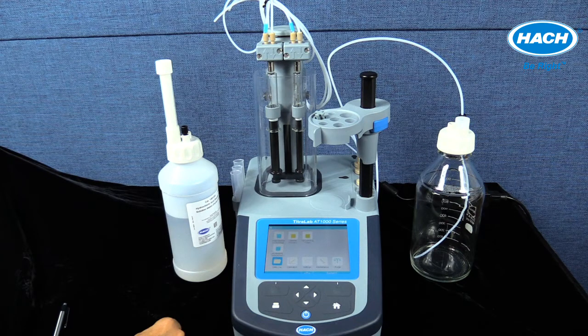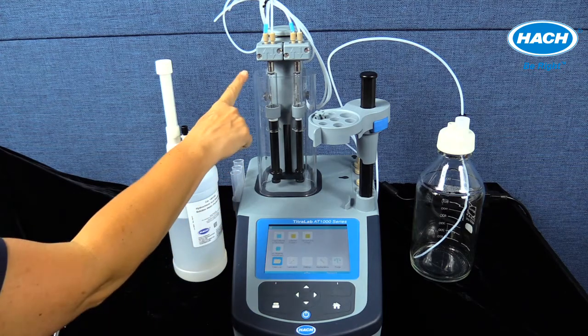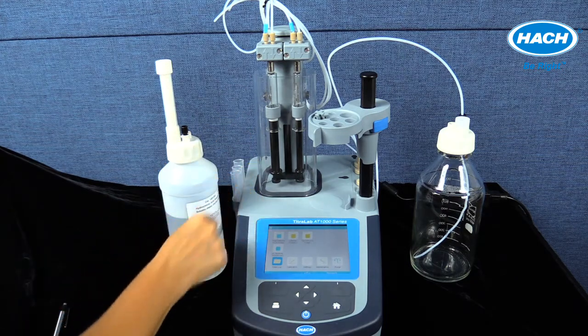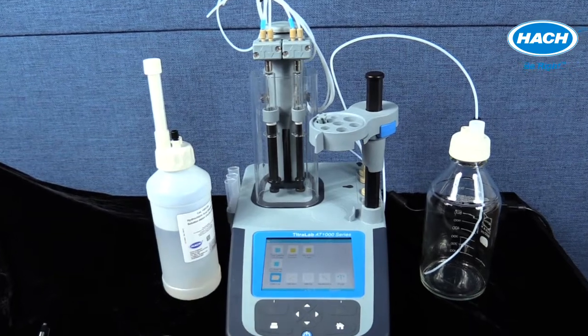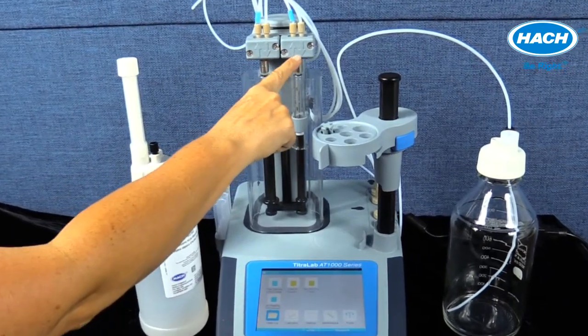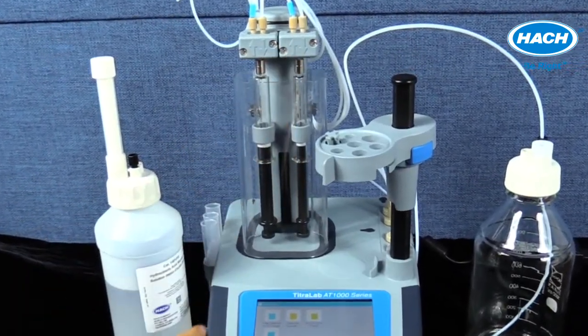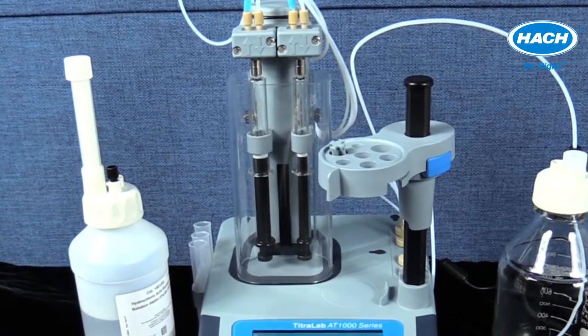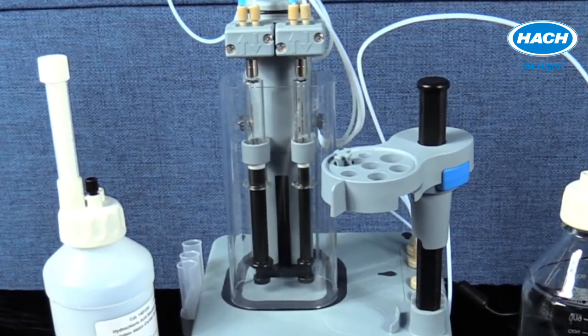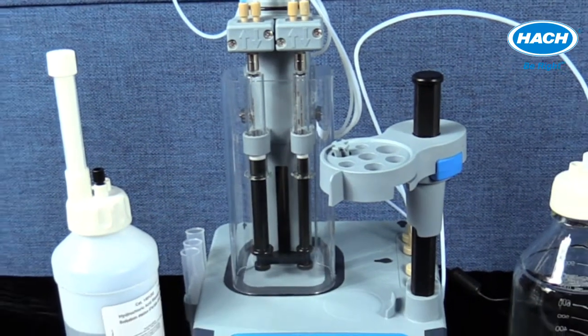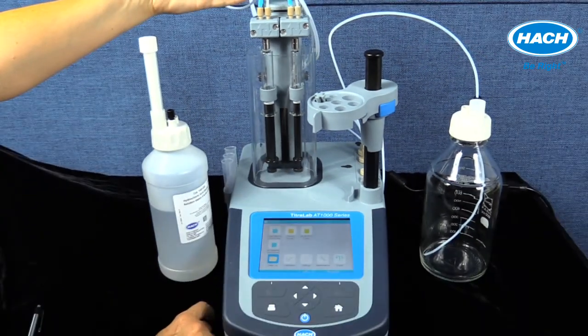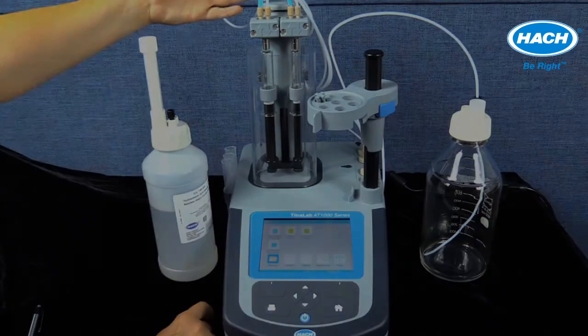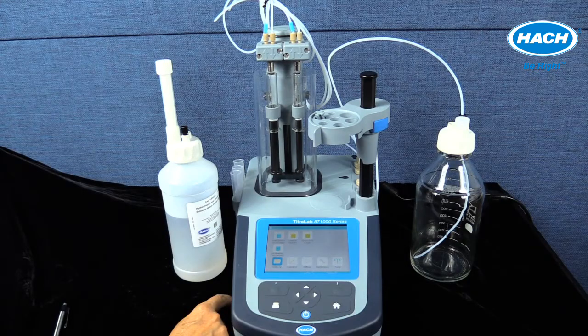For a titration to be accurate, the volume of a titrant being added or dispensed to the sample has to be precisely measured. The AT1000 utilizes a high-quality Hamilton syringe, also known as a burette, and a syringe motor with micro-stepping technology. AT1000 models are available with single or dual syringes. Each syringe has a built-in valve that can divert or stop flow from the syringe. This allows the titrator to utilize different titrants and have access to multiple applications and analyze multiple parameters.